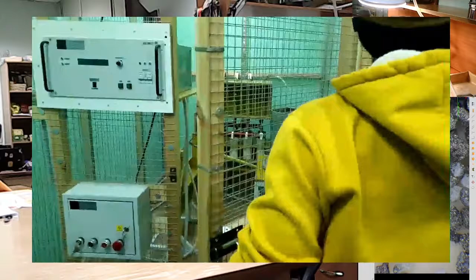These spark gaps are usually covered by the front panel, and here we're not covering it. There are also holes from one side and from the other to suck up the ozone, because air, once it's affected by spark gaps, becomes other gases like nitrogen and ozone, and you need to evacuate these gases out of the spark gaps. Otherwise it gets energized, electrized, and it doesn't work properly.